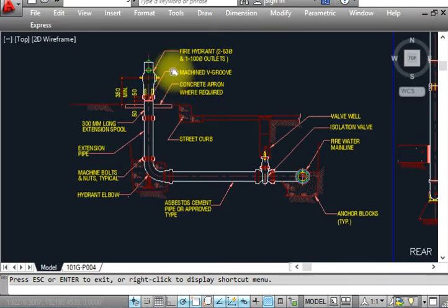So basically these are the main things. And a fire hydrant covers 120 to 200 meters everywhere. You will find it, for example, installed here. After 120 meters, 180 meters, or 170 meters, minimum 120 meters, we have to place the next one, so the firefighter can come here.